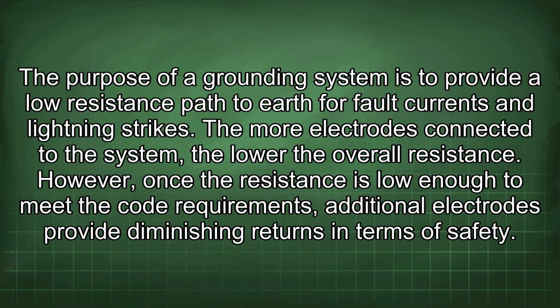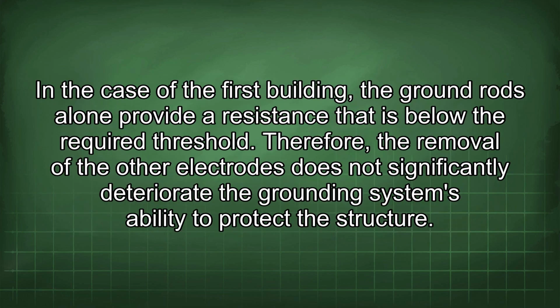The purpose of a grounding system is to provide a low resistance path to earth for fault currents and lightning strikes. The more electrodes connected to the system, the lower the overall resistance. However, once the resistance is low enough to meet the code requirements, additional electrodes provide diminishing returns in terms of safety. In the case of the first building, the ground rods alone provide a resistance that is below the required threshold. Therefore, the removal of the other electrodes does not significantly deteriorate the grounding system's ability to protect the structure.